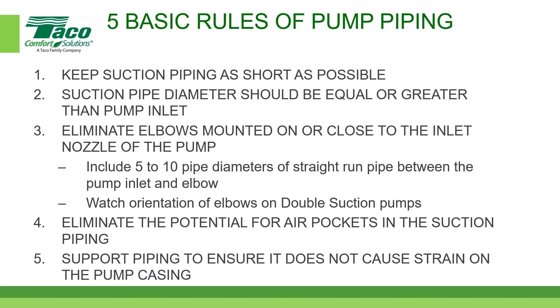And this is what I was talking about, right? So it depends on which way you're going. You've got a eccentric elbow reducer here. If the fluid is coming from below or straight in, you want the flat on top. That gets you a nice flow going into here. If it's coming down, which is probably the more common one, coming down from the top, you want the flat on the bottom here. So that will avoid an air pocket at the pump suction and allow air to be evacuated. You can see that there.